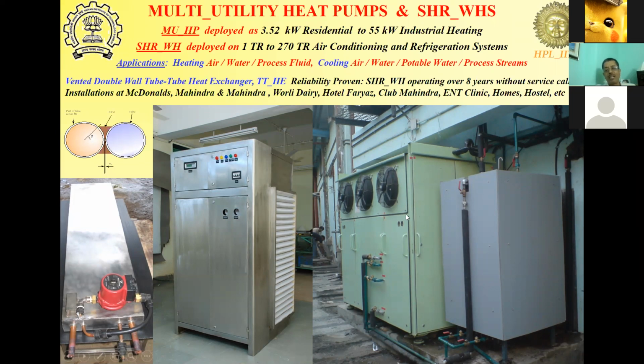Then we had also deployed a 24-ton evaporatively condensed multi-utility heat pump in McDonald's. In this particular case, it was giving DX cooling, that is direct exchange cooling, in the kitchen. So the liquid refrigerant supplied to the kitchen air handling unit would be coming from this unit. And the evaporated refrigerant vapor will then come back into this, and it will be compressed using the compressors present in this unit. We had two 12-ton compressors present in this, and these two 12-ton compressors would then compress the refrigerant to the condenser pressure.